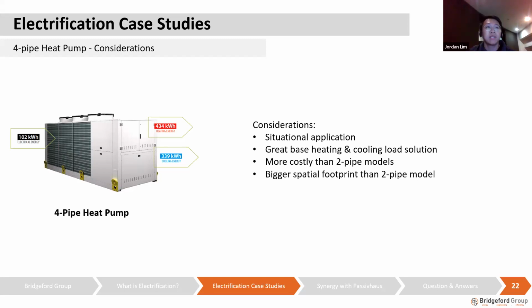So you can see that this type of unit can be applied at, say, aquatic centers, for example, where you would constantly be needing heating for the pools, and then cooling. For aquatic and leisure centers, they've got gyms that constantly need cooling regardless of whether it's winter or summer, because of the human heat load, because of the latent heat that's constantly supplied due to metabolism.